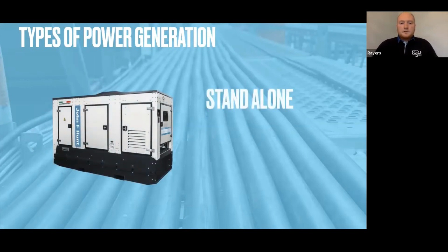Types of power generation - I'll refer to diesel machines for now, with three examples of generator setups. First, standalone: a plain old diesel-fired generator with an alternator, an engine, a control panel, and a source to plug your cabling in to deliver power. It's a straightforward, self-contained system compared to other options I'll show you, giving perhaps less fuel consumption, but with drawbacks - there's no redundancy and it has fixed capabilities. Unlike a hybrid unit, imagine turning your car on just to charge your phone - that's constantly running. Whereas with a big battery, we only take the power we need. This generator only does one thing, and it will only be a 60 kVA or 100 kVA machine. That's standalone.